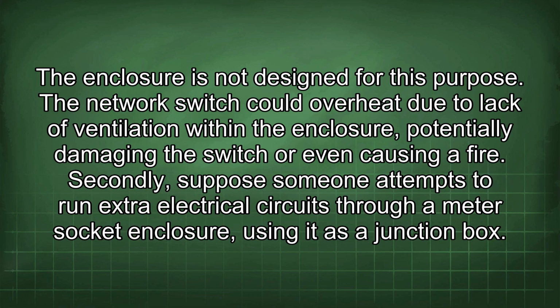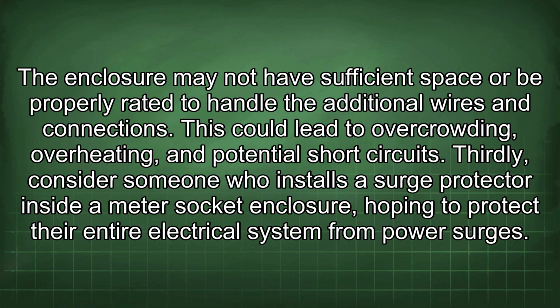Secondly, suppose someone attempts to run extra electrical circuits through a meter socket enclosure, using it as a junction box. The enclosure may not have sufficient space or be properly rated to handle the additional wires and connections. This could lead to overcrowding, overheating, and potential short circuits.